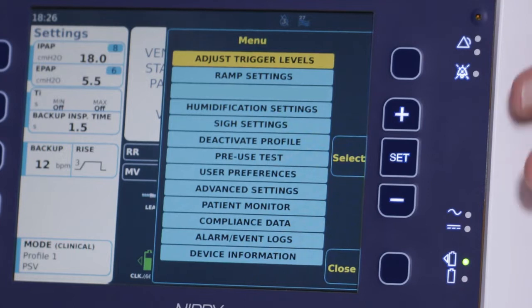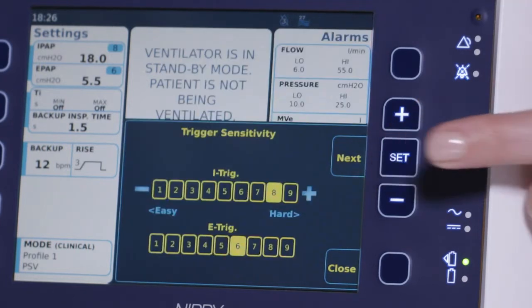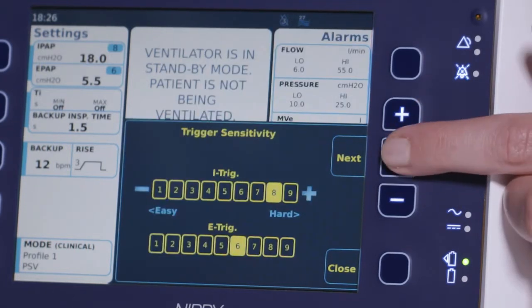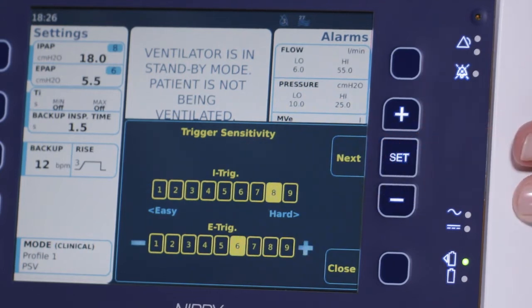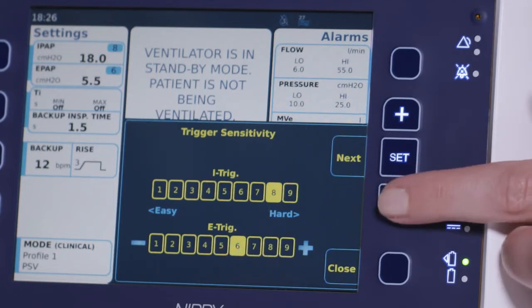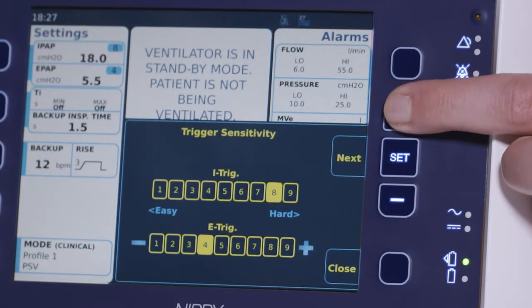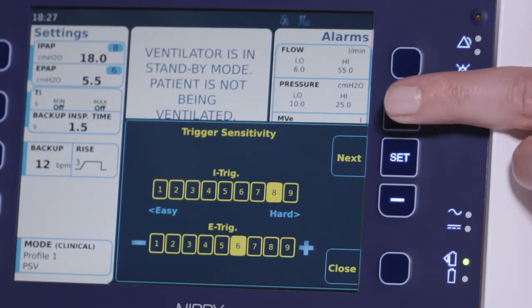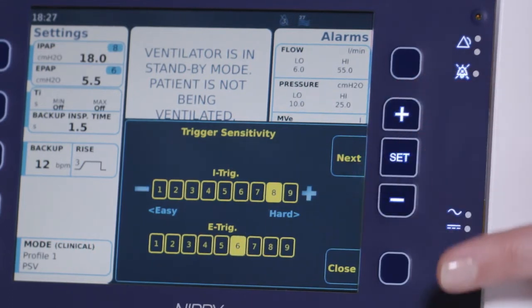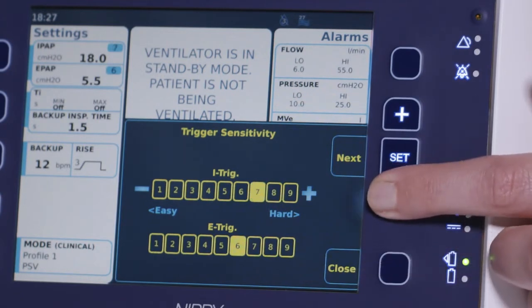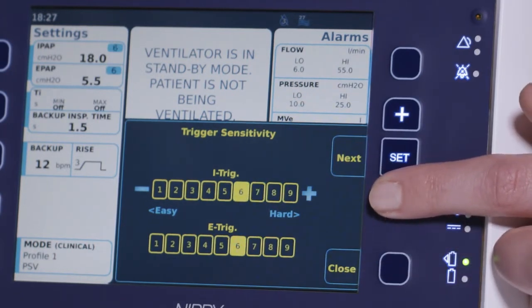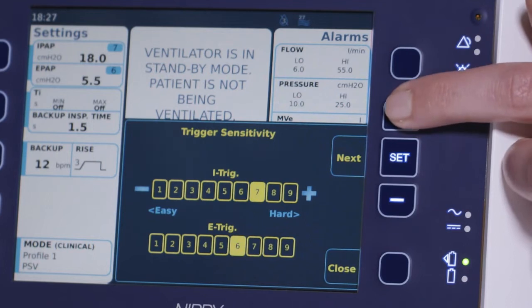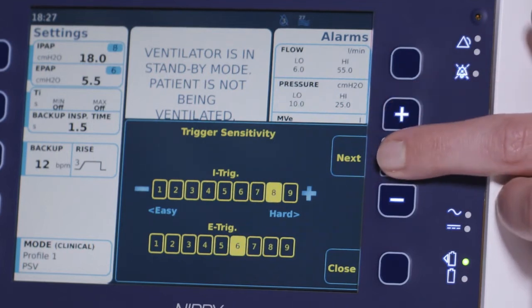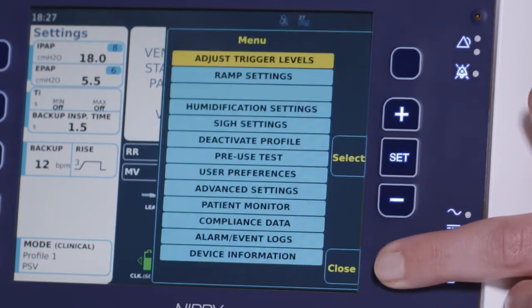There is an option to adjust the patient's eSync trigger settings. Press the Set button to move between the trigger options, and then the plus and minus buttons to change the trigger values. In supported breath modes, you can change both the inspiratory and expiratory trigger values. In controlled modes, you can only set the inspiratory trigger value. The trigger values range between 1, being the most sensitive, and 9, being the least sensitive.